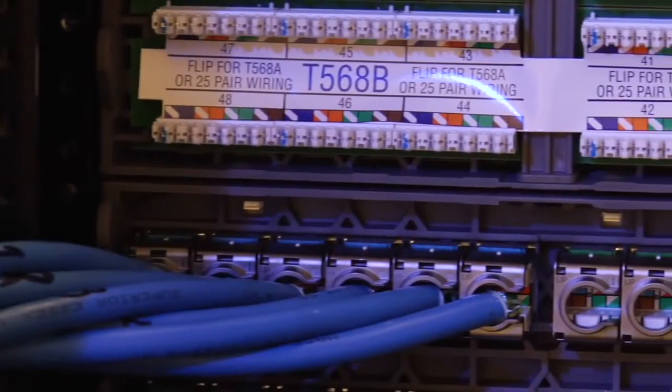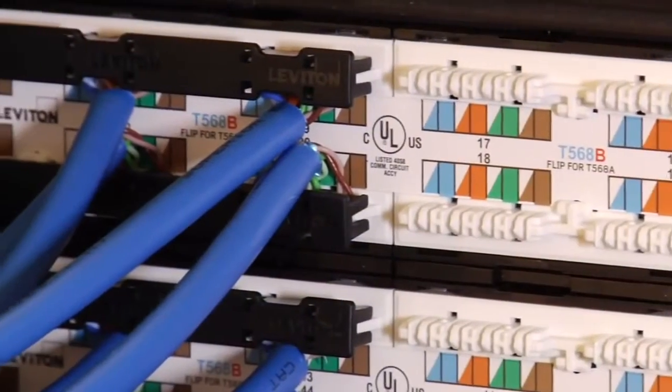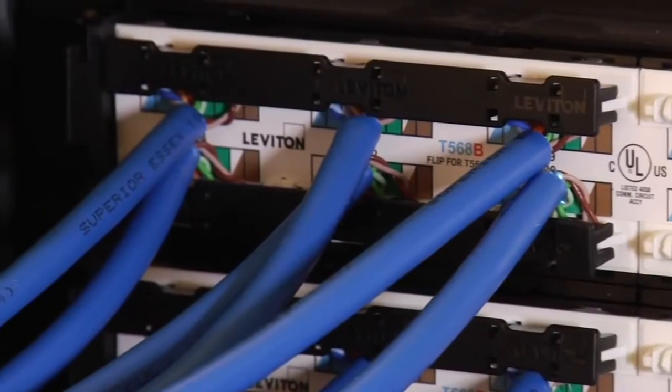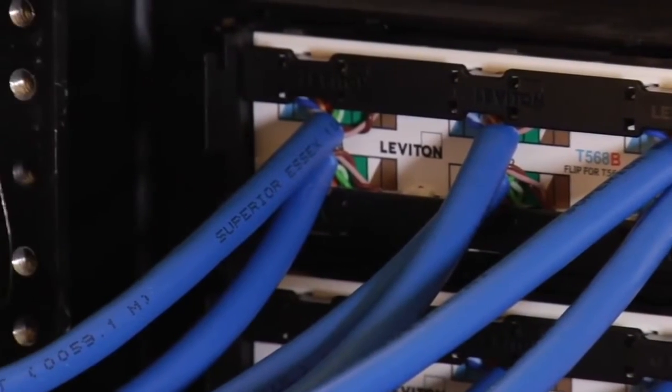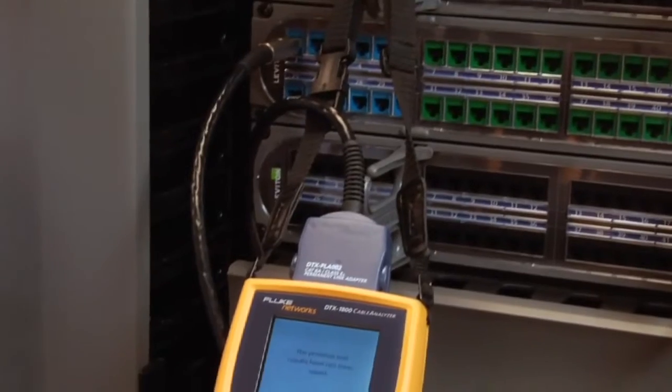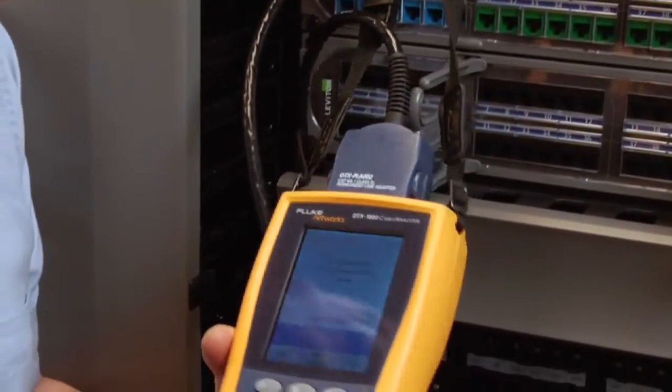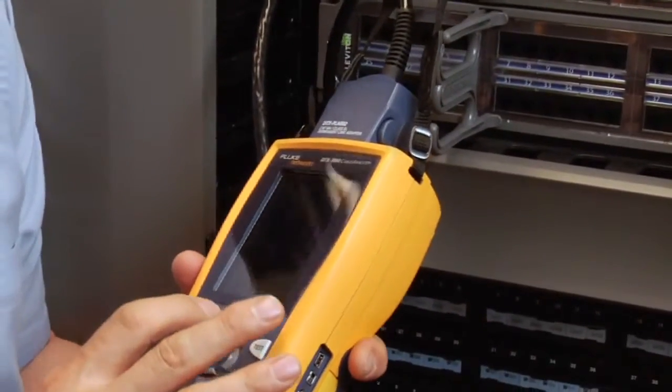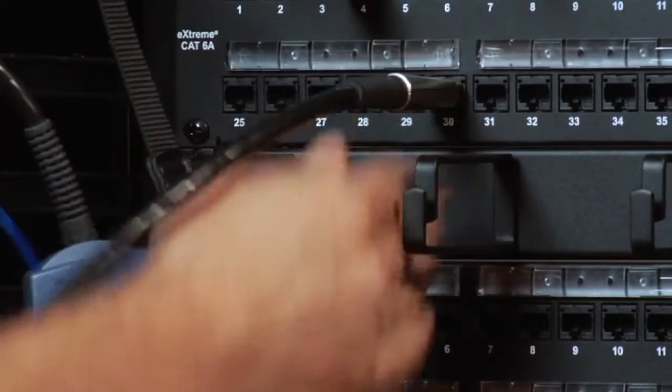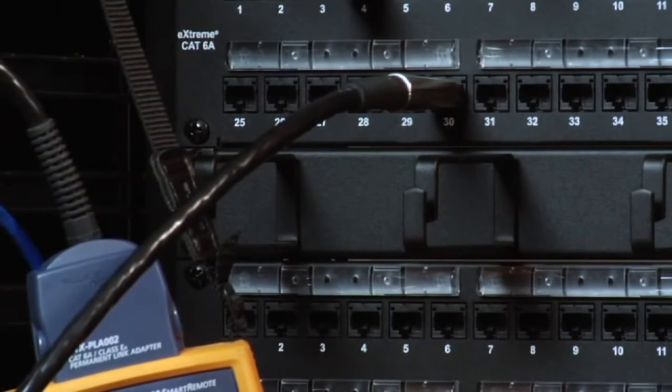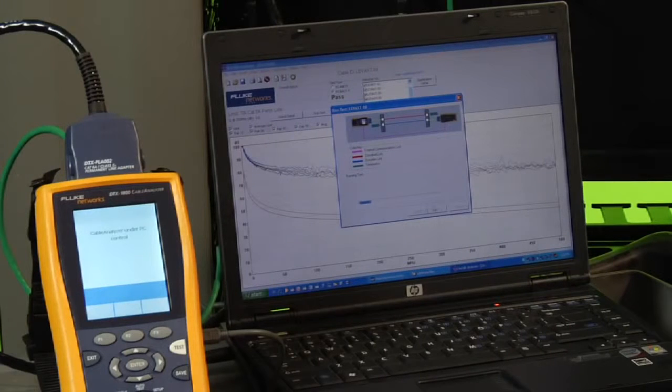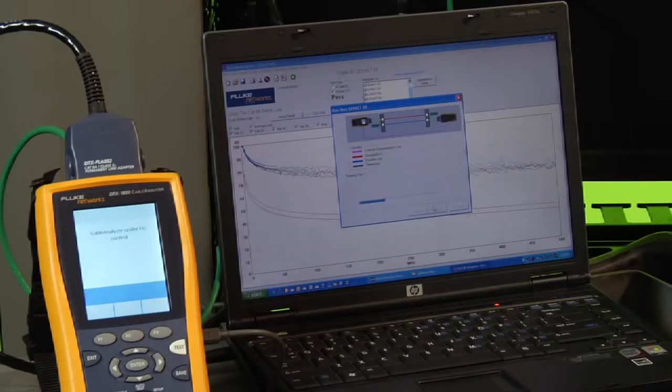We're going to start by running our normal permanent link or channel measurements. The tests you already run on each cabling link in every new install. There's nothing new here. You're going to follow the exact same procedure you would for any new CAT 5E or 6 installation. This part of the procedure ensures that each link is performing correctly on its own. After we complete that task and have saved the results, we're ready to start alien crosstalk testing to make sure these cables aren't interfering with one another.